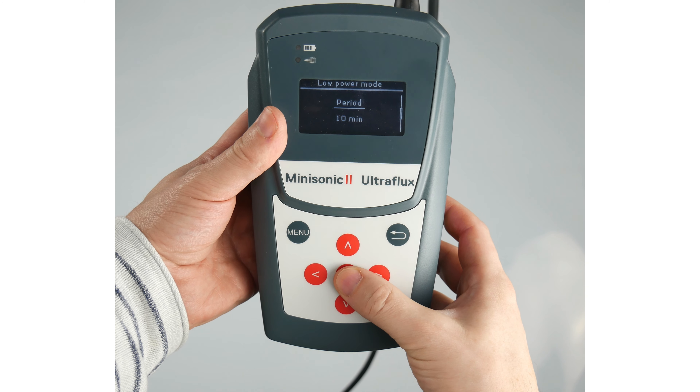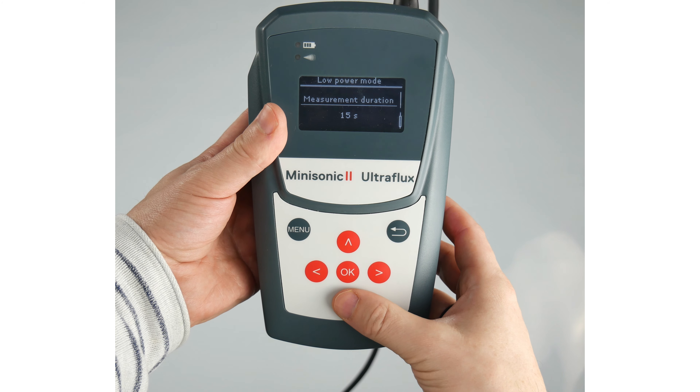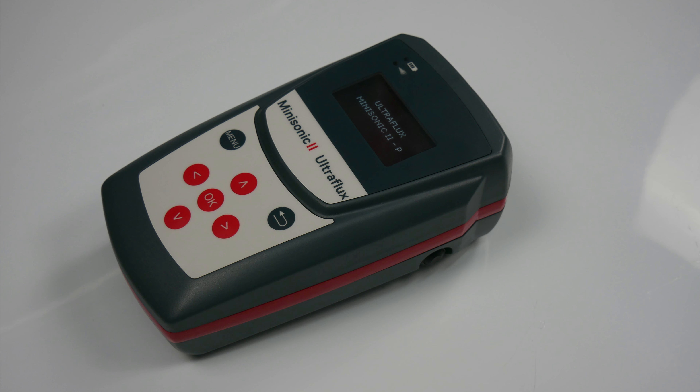The Mini Sonic 2 Portable has an internal battery that will last an entire day of continuous operation, but if you need longer than this it can be externally powered. When external power is not possible, you can use the low power mode that will wake the meter up at a user defined interval, log the flow measurements and then power down until the next interval. Very useful for long-term remote flow monitoring.